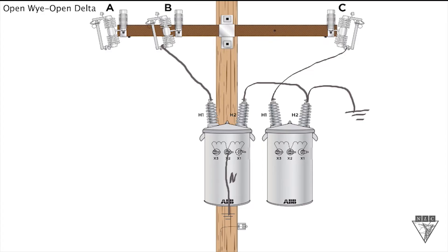Now what we need to do is tie the X1 bushing to the X3 bushing. Once you've done that, now we can run our hot legs down. Off the center phase is going to be our hot legs. There's your two hot legs. I'll label an H.